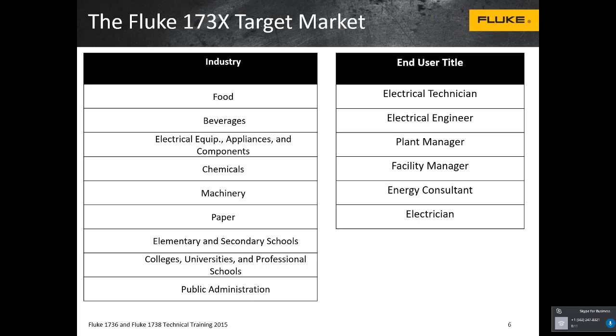So all of these are reasons why you would use it. Also, sometimes circumstances arise where you have an electrical panel and somebody may want to add some temporary load to it, but we're not sure if it would compromise the existing design of the panel. So a load study could be done to determine feasibility of adding additional load, even on a temporary basis. That's probably one of the most common applications we're asked about - trying to see how much load there is. All the 173X series have the capability to do that.